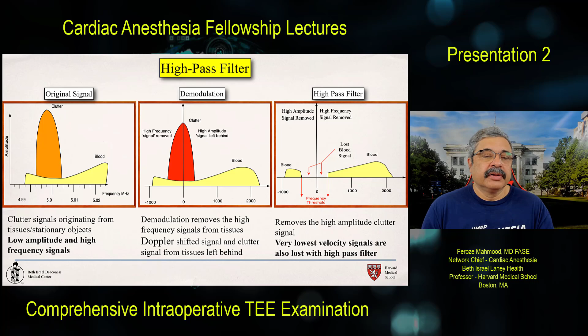So the original signal is received as clutter and meaningful signal. The process of demodulation removes the high frequency signal, and the high pass filter removes the high amplitude signals in the last phase, to leave what remains as the Doppler signal. Complicated physics, but based on what controls you see on the machine, these are important things to know.